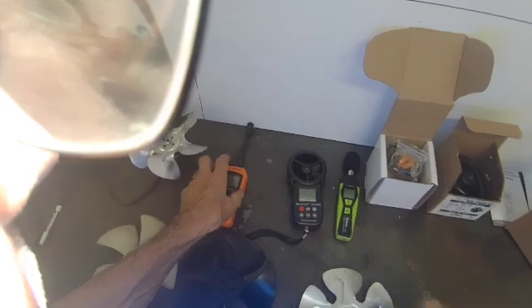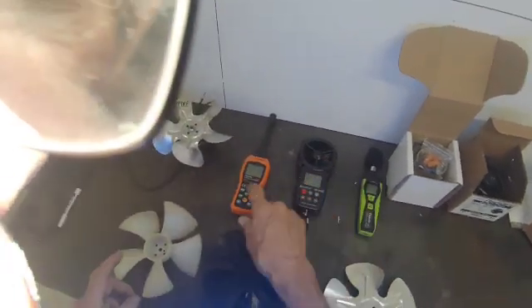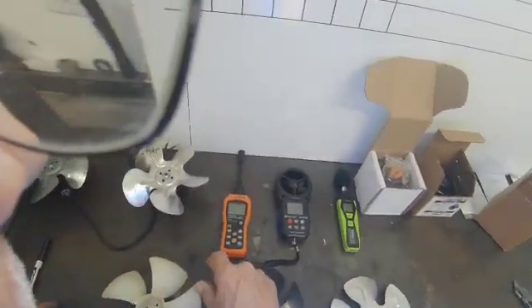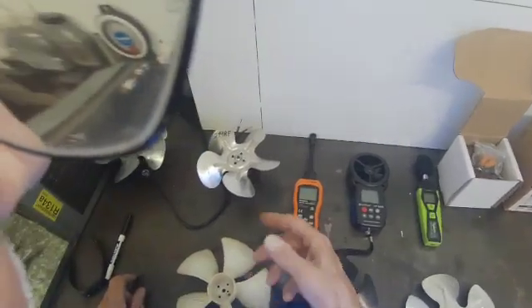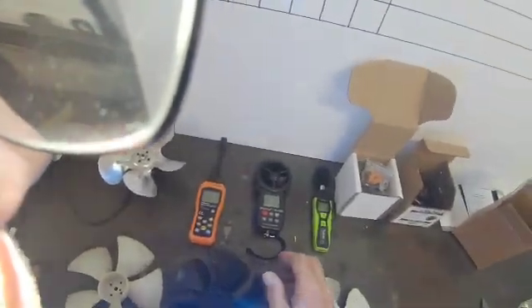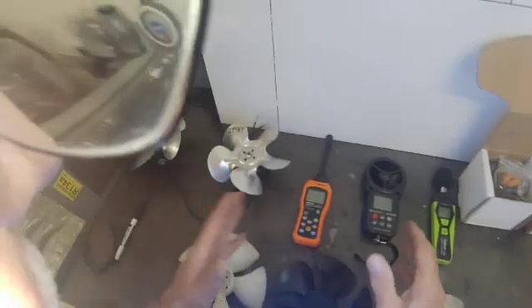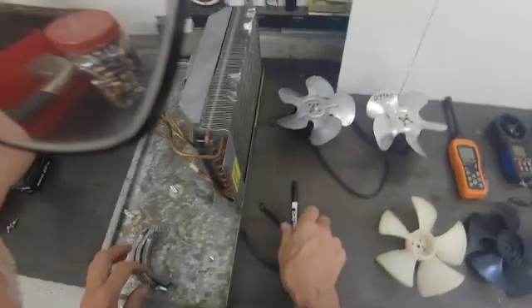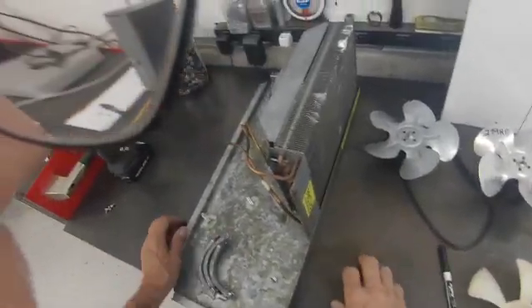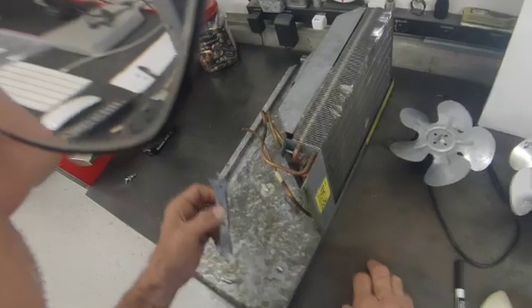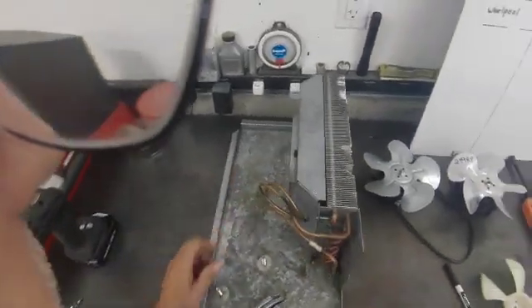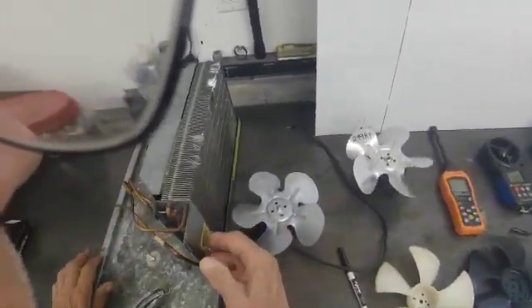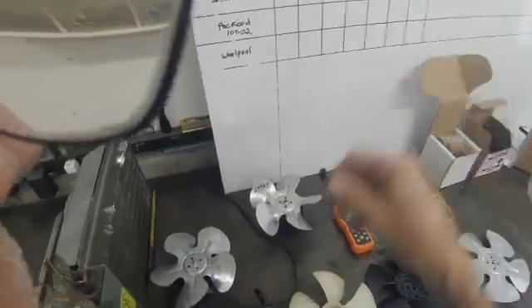We bought these meters here. We have a tachometer, we have an anemometer. The tachometer will measure the speed of each motor against its advertised speed. The anemometer will measure the wind power and how much air is being pulled through the condenser and doing the proper cooling. And then this is a decibel meter, and this is going to measure the sound. So what we'll do is we have this mocked up condenser over here that we took out of a bottom BFI, and we're going to mount each motor onto this condensing unit, and we're going to measure the wind velocity through the condenser and the sound level, and then I'll post it up on this chart.